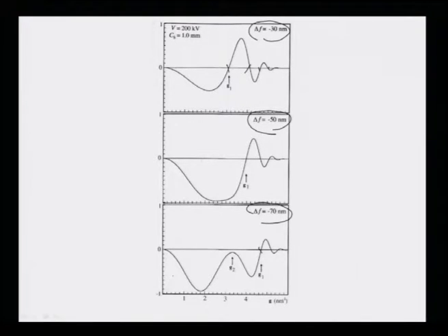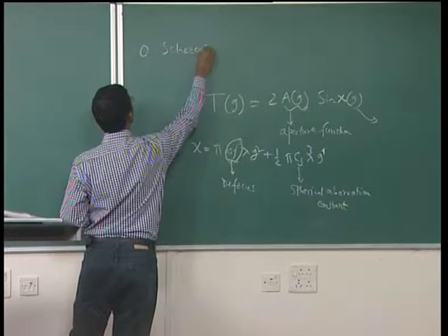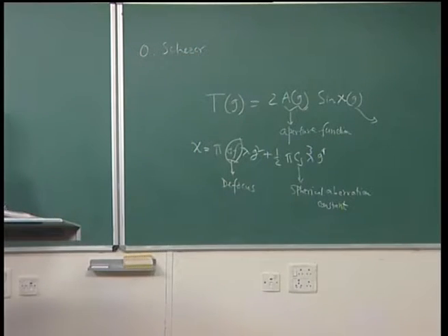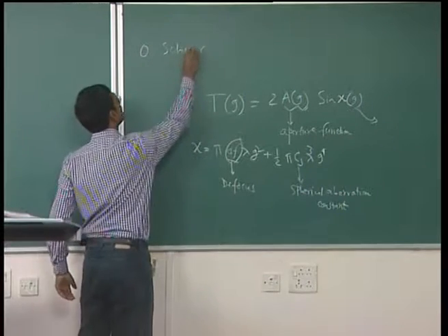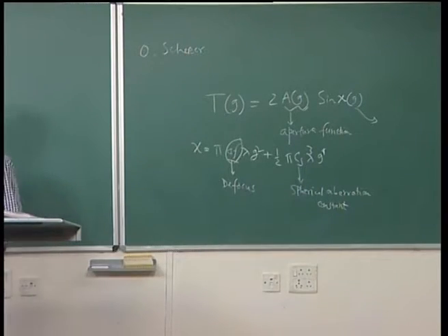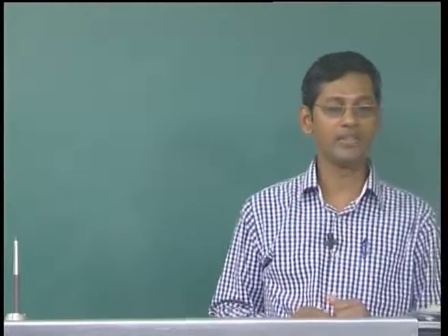So, what Otto Scherzer has done, long back in 1949, is he described the optimization of the focus or defocus in a particular microscope. What he said is that the transfer function can be optimized by balancing the effect of spherical aberration against a particular value of defocus.